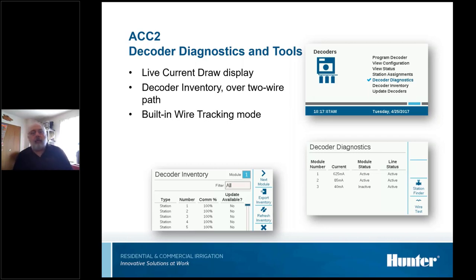It's got a built-in wire tracking mode. Basically, it gives us the ability to change the output of the module from that pulsating DC voltage to 24 volts AC, and then standard test equipment works for troubleshooting purposes. And then it's got a station finder, or a chatter function. Basically, this turns the output of a decoder on and off at a one second rate, and it makes the valves chatter or vibrate. It helps find valve boxes that are under mulch or under vegetation when you can't find the box. It's not perfect, but I found quite a few valves that we couldn't find any other way with the chatter. The I-Core dual system also had that.